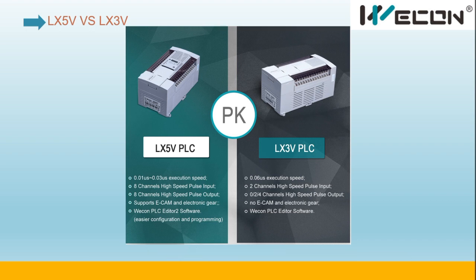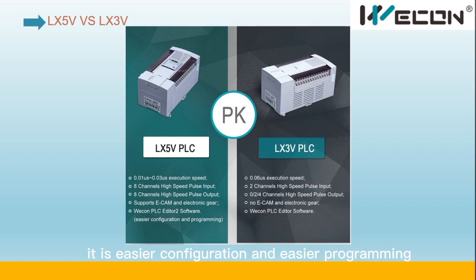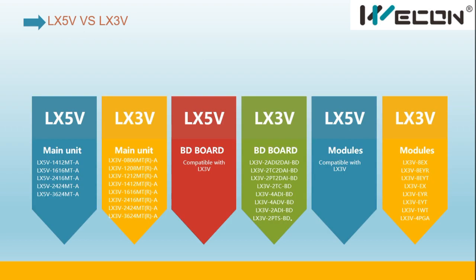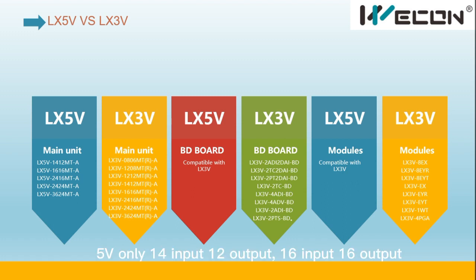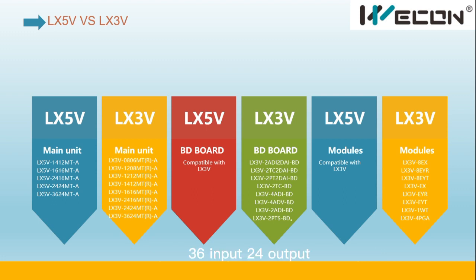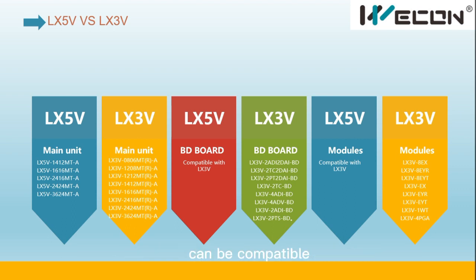The standard LX3V PLC has no E-cam or E-gear support, but on the LX5V they are fully supported. The software is also different — LX5V uses PLC Editor 2, which offers easier configuration and programming. Regarding main units, LX5V has five options: 14-input/12-output, 16-input/16-output, 24-input/16-output, 24-input/24-output, and 36-input/24-output. LX5V PLC is fully compatible with LX3V PLC.